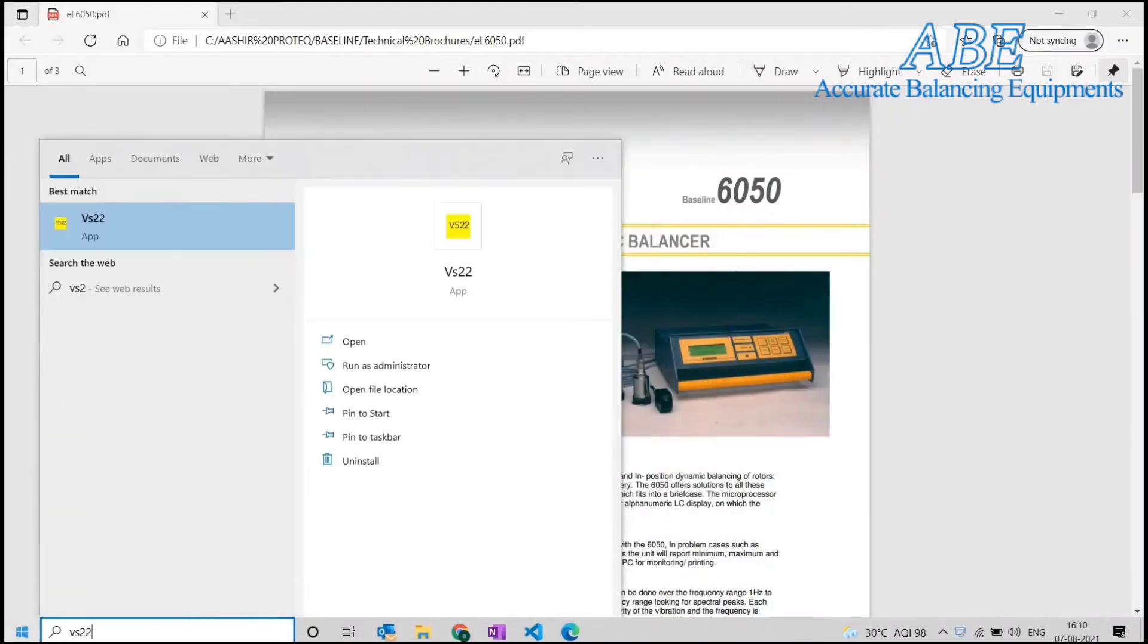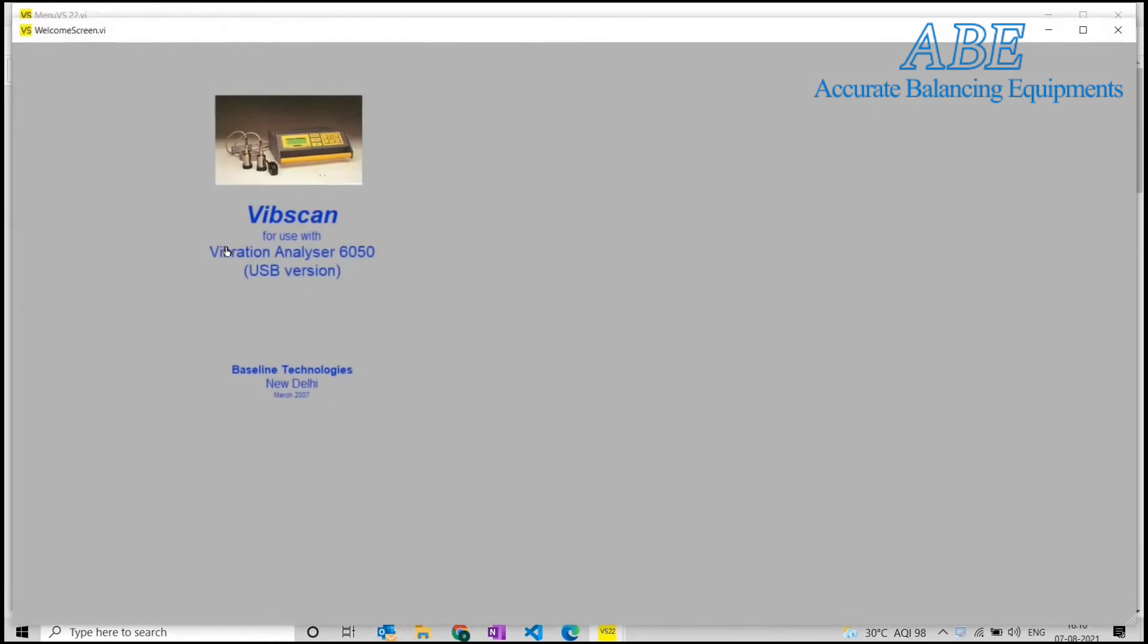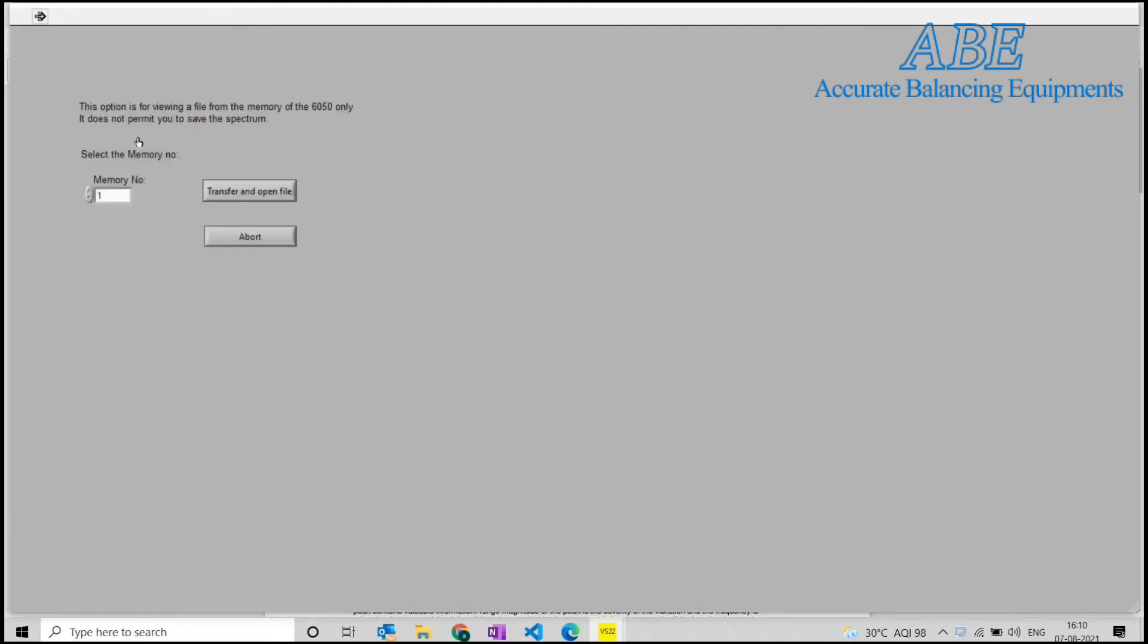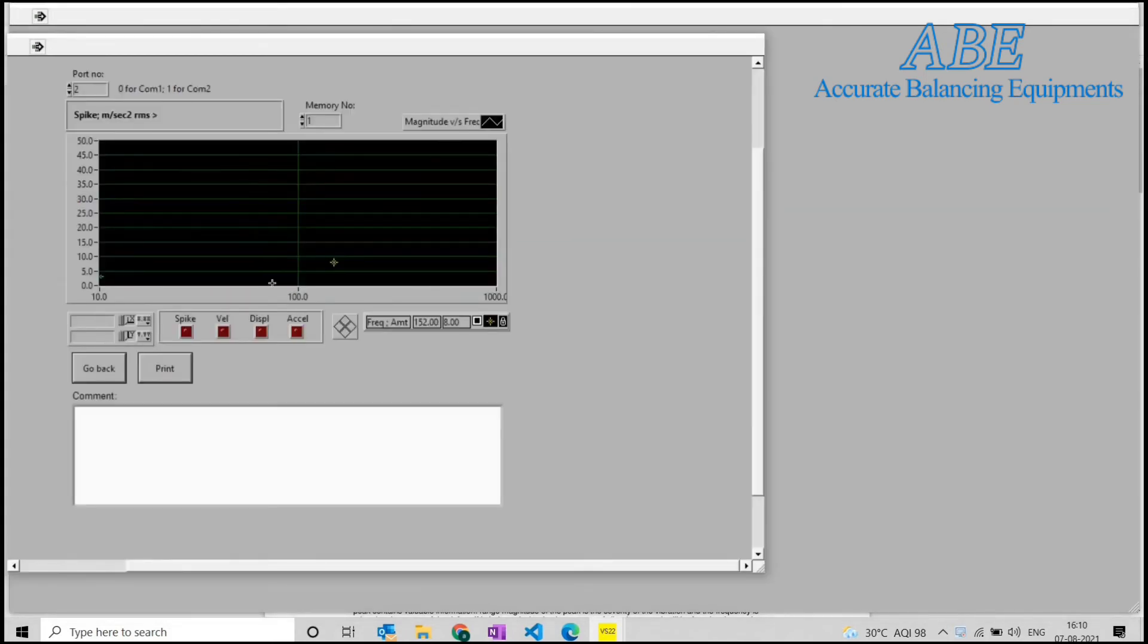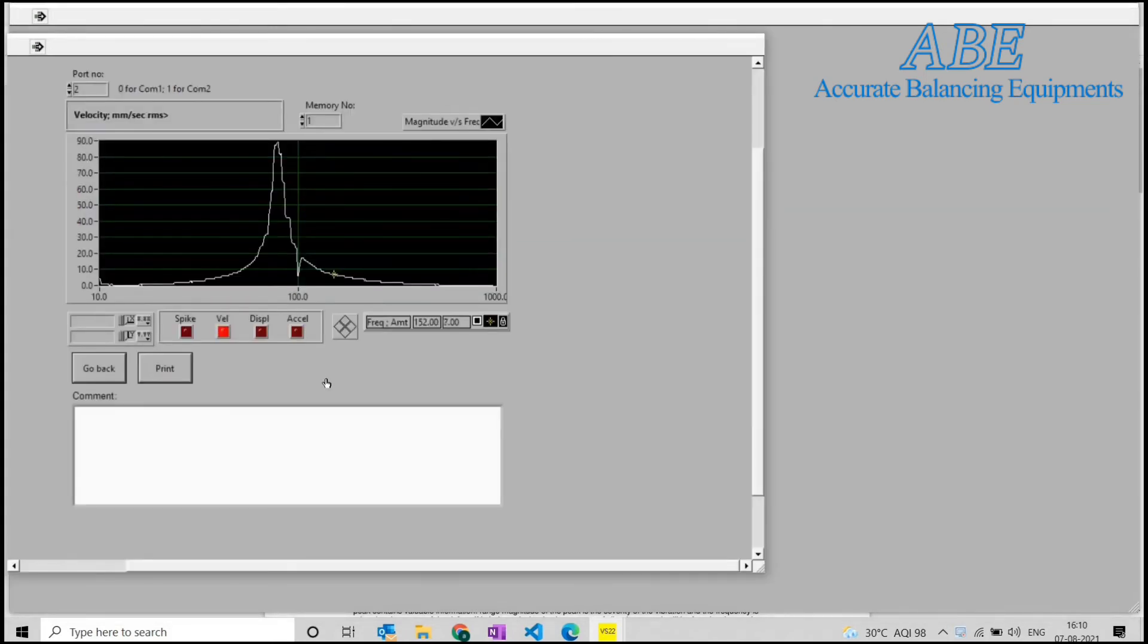Vs22 is a PC-based software developed by Baseline Technologies. In addition to file storage, it also enables spectral enveloping and spectral trending, adding immensely to the power of frequency analysis of the unit. The simplest way to view a spectrum on the PC is to transfer via memory number. This option will not save the file on the PC and should be used only for quick viewing of the spectrum.